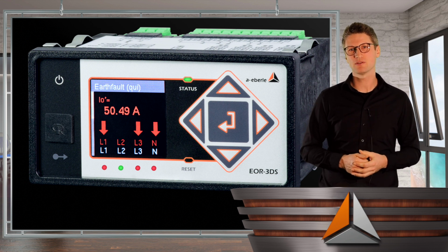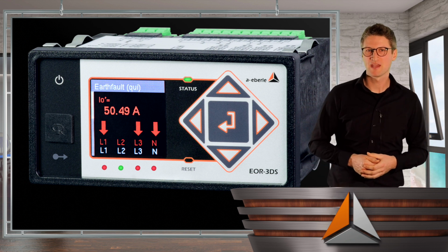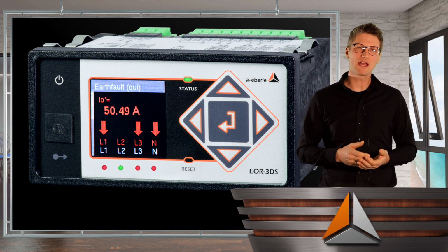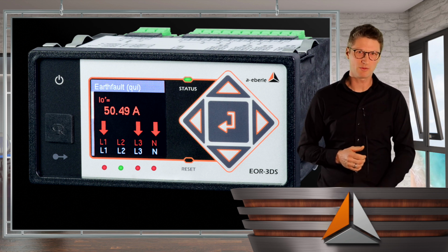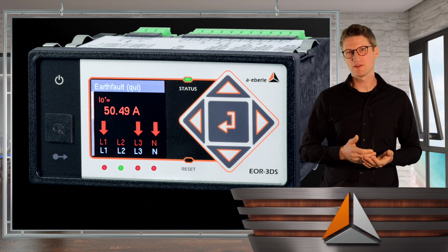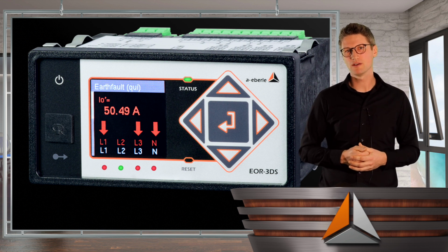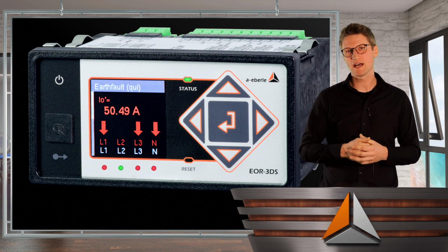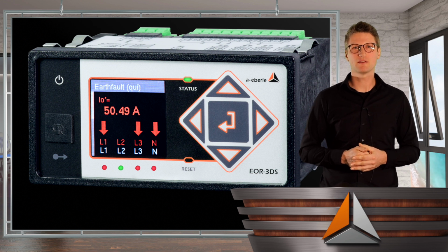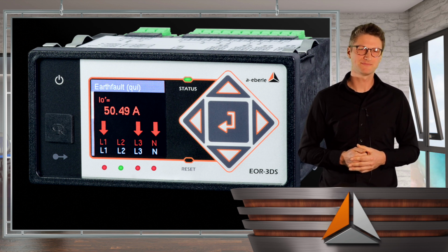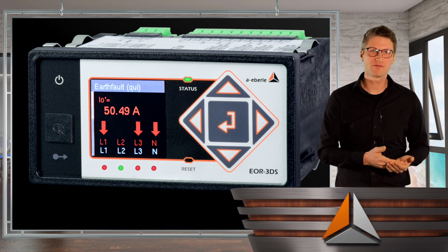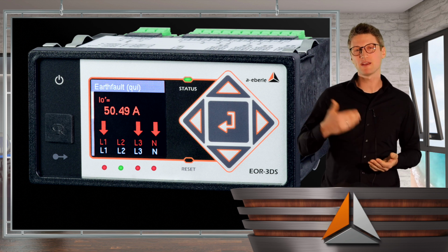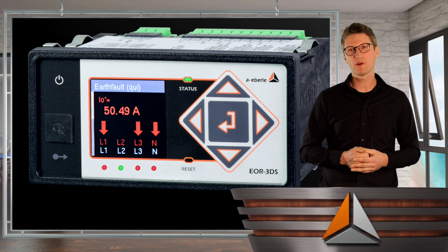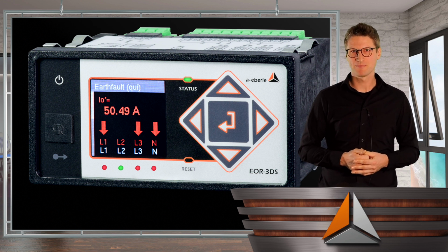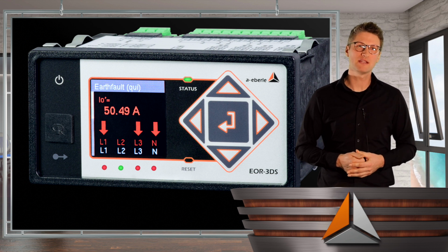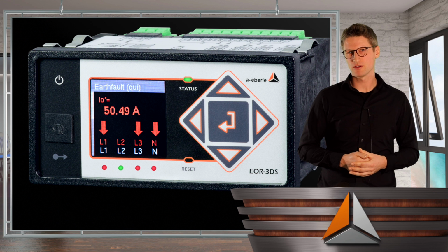Yeah, let's come from simple analog secondary substation to digital secondary substations, where we see our EOR3DS as a digitization unit for these secondary substations. The aim of the device is monitoring and control of important junction points in the grid. What are the key facts of digital secondary substations? On the one hand, they are remotely reported. So you get a complete condition diagnosis of the substation and measurement values of this special important grid node. On the second hand, you have the station remotely controlled. So nobody has to go there to switch in and switch out the load breaking switch, but you can do it from a central SCADA system. And these load breaking switches can be additionally supervised regarding safety and monitoring functions.